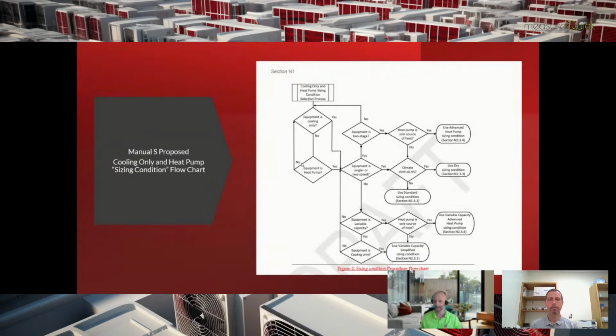I'm not going to read everything up there, but if you follow the lines and follow the logic, it is the correct way to think about this stuff, especially when we get into the actual new Manual S, or the proposed Manual S. So as you can see, this is sort of the procedure list for sizing. It's the 1, 2, 3, 4, 5, 6, 7, 8, 9, 10 steps to sizing a heat pump. And you'll see step 2 says when the heat pump equipment is used, determine the sizing condition. There's that terminology again. So Manual S defines sizing condition as: air to air and water to air conditioners and heat pumps shall be sized for the operating condition that corresponds to the project design. And they outline, as you'll see, several operating conditions that you have to match up to what you're actually trying to size the heat pump for.